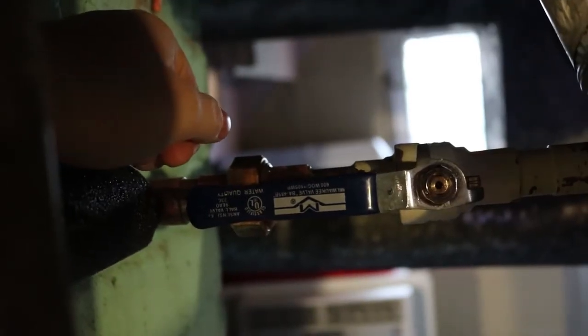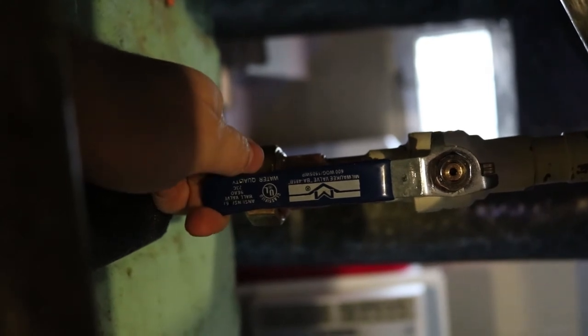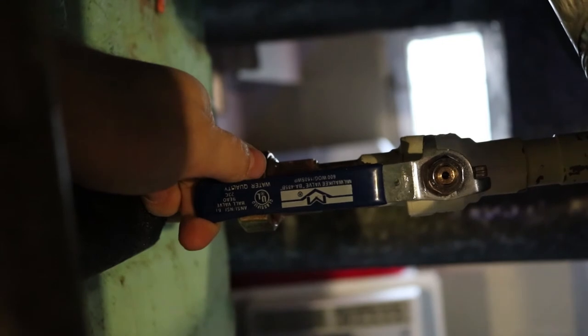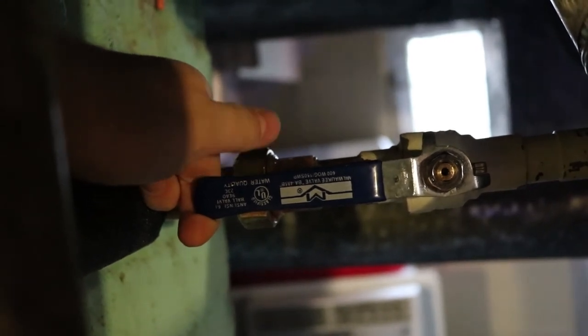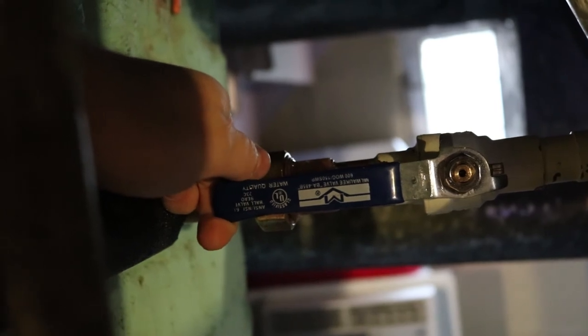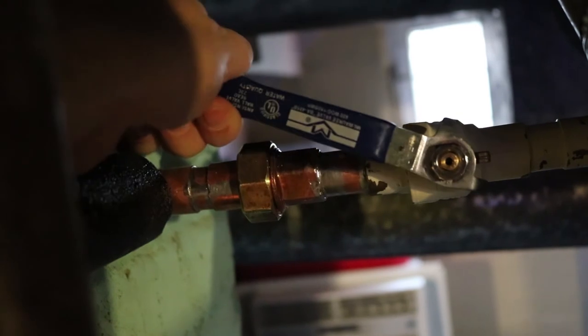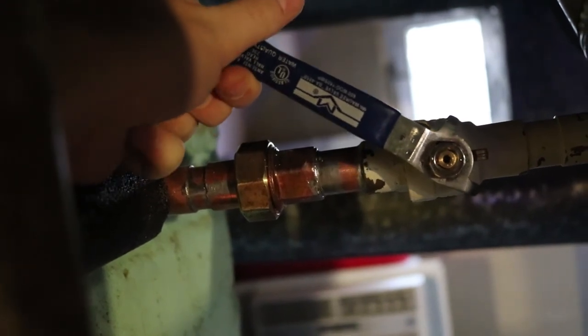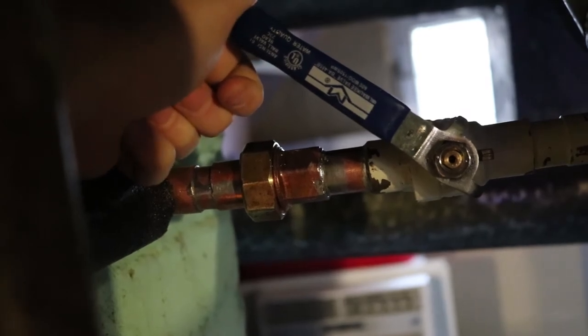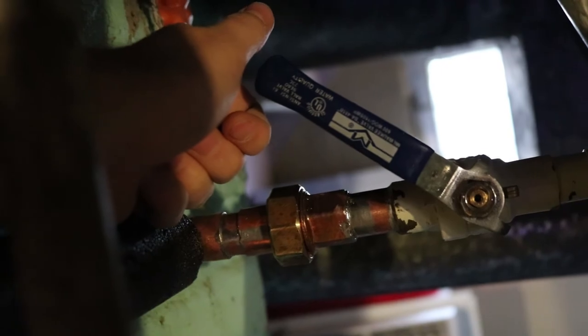The pump is actually heating a little faster than I would like, and I think I'm going to try to throttle it back a little bit with the return valve. I'm using the return valve for this because pumps generally like back pressure better than they like being throttled back on their intake. So I'm going to turn this maybe to half off, something around there. I'm going to see what that does to the rate at which my heater is heating my tank.